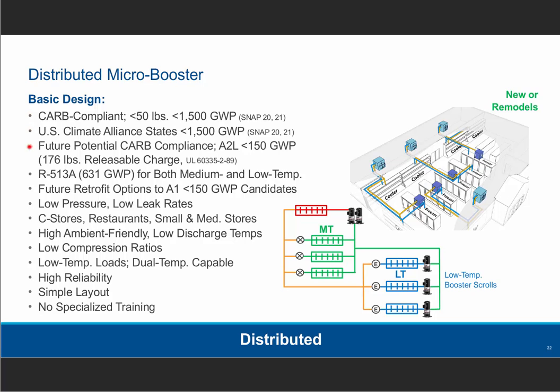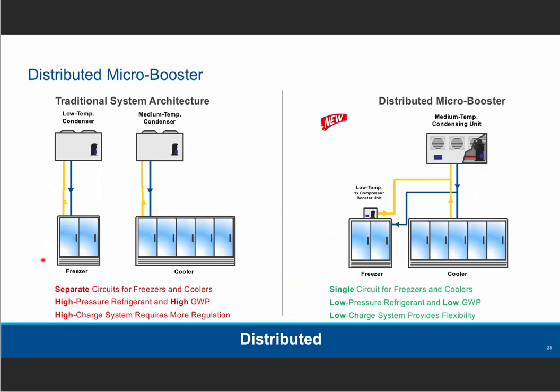And as I mentioned before, future potential for A2Ls as well. This architecture has been really leveraging the use of low pressure refrigerants for an architecture that can do low temp as well as medium temp with low pressure refrigerants. And I'll talk a little bit more about that in the diagrams to come. So the schematic on the left is your traditional condensing unit I just talked about. The one on the right is micro booster, distributed micro booster, where a condensing unit will have typically two compressors at minimum in here, one being variable capacity. Discharge liquid line here is in blue, feeding a medium temp. The liquid line also feeds the low temp. Low temp comes out and now goes into the compressor which discharges into the closest medium temp suction line.